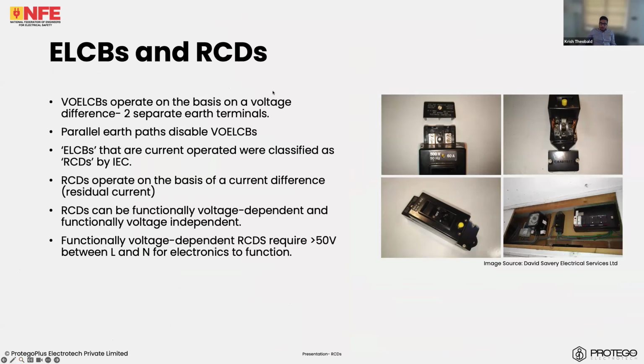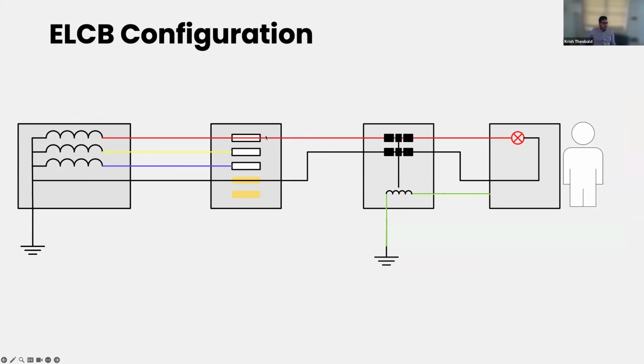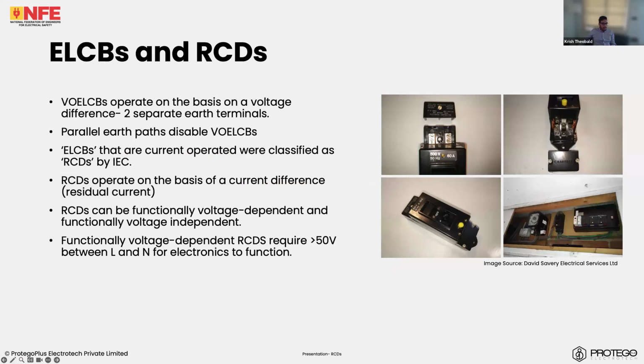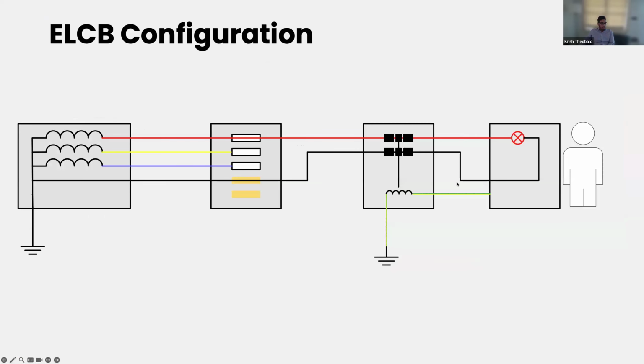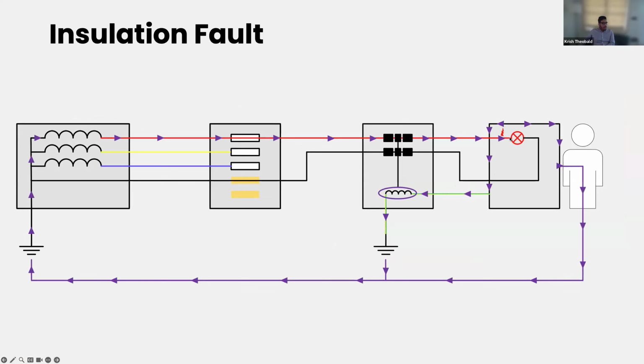There are two types of ELCBs, voltage operated and current operated. Mr. Gopakumar has already explained the current operated. It's very important to understand how these work. You have a supply, a load, the ELCB, and there is a coil inside the ELCB connected to an earth electrode. The PE conductor goes through the ELCB, so there's an in and an out. That's why there is an in terminal and an out terminal as well for the earth conductor. What happens is, if you have an insulation fault, then you have current flowing through the body of the equipment back to the source. It will be through a person touching the equipment and to the PE conductor.